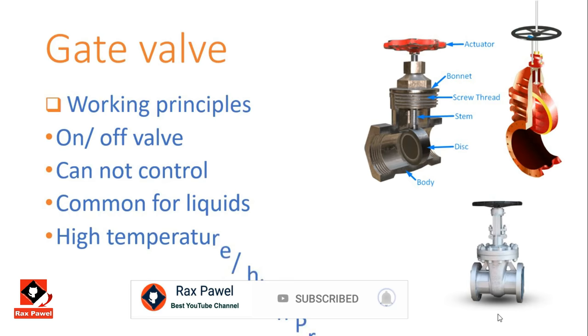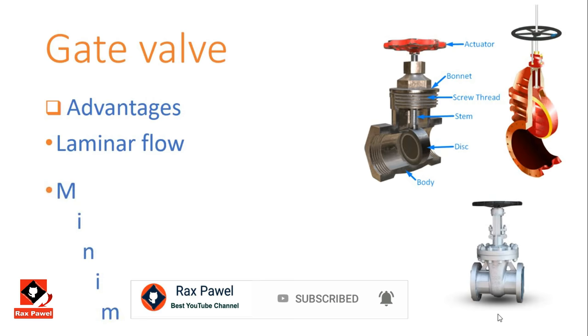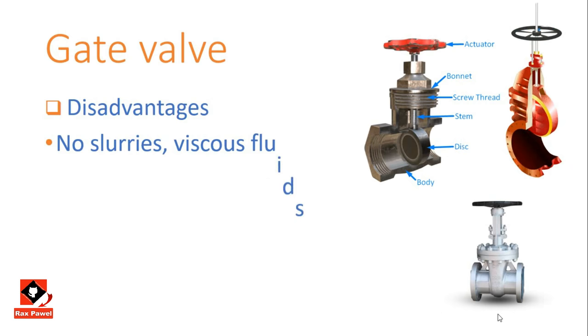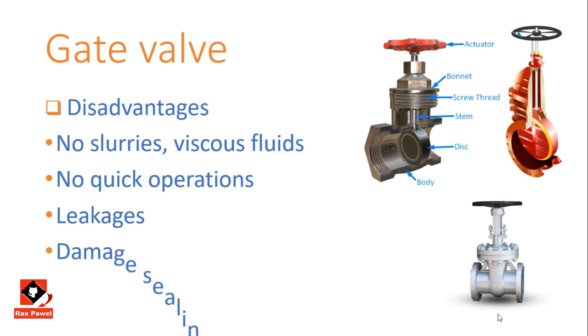Advantages of the gate valve: it provides laminar flow, giving minimum pressure loss when fully open, and tight sealing when fully closed. It can also be used in both directions. Disadvantages: the gate valve cannot deal with slurries or viscous fluids and cannot operate quickly. Leakages may occur due to load, and sealing surfaces can get damaged due to friction.